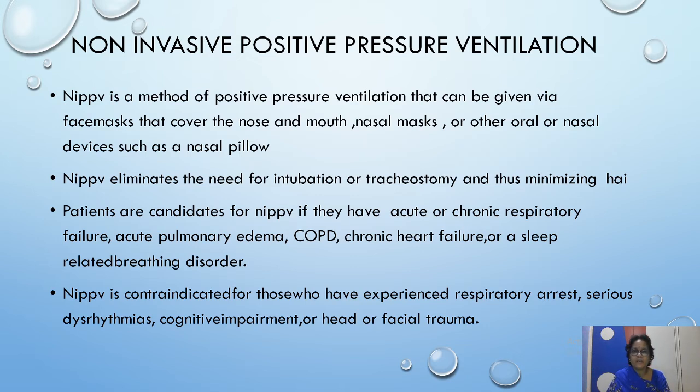See, in the previous types of ventilators, we have seen that the patient requires endotracheal intubation or tracheostomy. They are invasive. Here, in the case of non-invasive positive pressure ventilation, there is no such endotracheal intubation or tracheostomy. The patient will have only a mask, a face mask which covers the nose and mouth, or nasal masks, or other oral or nasal devices such as the nasal pillow. That can be attached to the ventilator and it delivers the ventilation. It ventilates the patient.